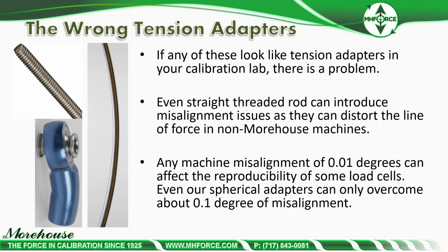You see high deviations, so it absolutely shows up in your calibration data, whether you realize it or not. You kind of need to know what a good load cell looks like, with the machine being plumb, level, square, and rigid, and with load torsion, versus a bad load cell. And then you need to figure out: was that load cell bad or were the adapters bad? Did the customer send in a bent rod? Because we measure them.